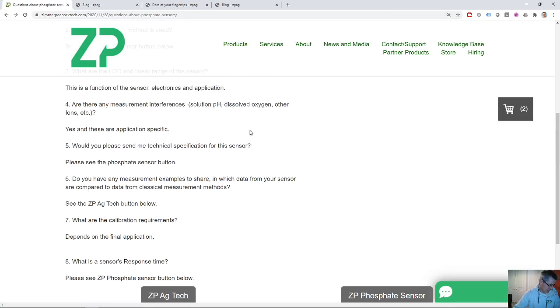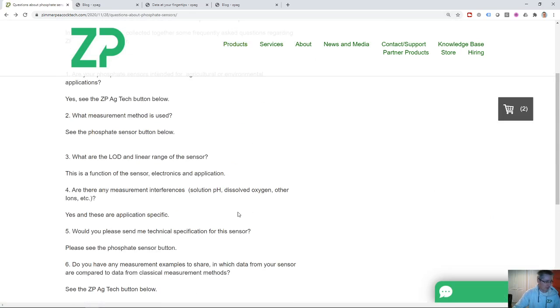The next question is, are there any measurement interferences? All sensors have measurement interferences. Whether they're important or not depends on the application of interest. For example, if you're measuring something in blood, then the pH is often controlled. So if your sensor is pH sensitive, it doesn't matter because the matrix itself is quite pH controlled. Now in terms of our phosphate sensor, there will be some of these interferences, and as we mature the sensor, we will be able to adjust for them or eliminate them. But I can definitely say it won't be oxygen sensitive, it won't be so much ion sensitive, and we will have to buffer the sensor for pH sensitivity.